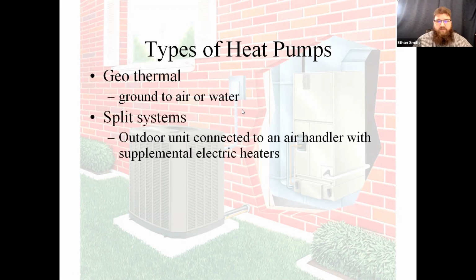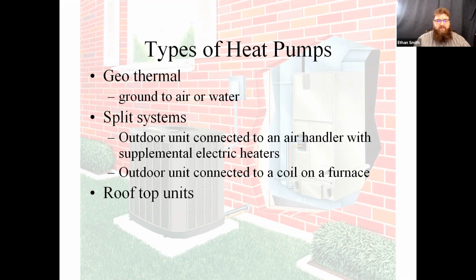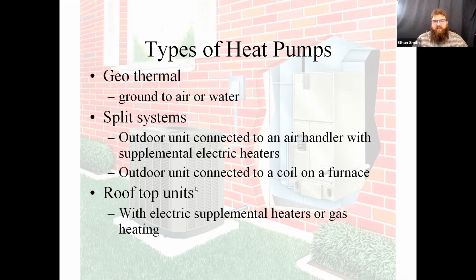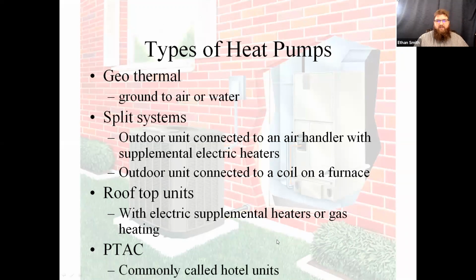A lot of these are split systems. Sometimes in the commercial world, you will see a packaged unit or a rooftop based unit that's a heat pump. Sometimes you'll have little in-ceiling heat pumps that are water to water, but they do have a refrigeration circuit in them. And of course, we've got rooftop units that are heat pumps that'll either have an electric backup, no backup, or a gas pack as well to run that heat on a rooftop supplied unit. Then, of course, we have the ubiquitous PTAC unit, and these are most commonly used in hotels. It's that little through the wall unit that will heat and cool the space. We see a lot of heat pumps there as well.